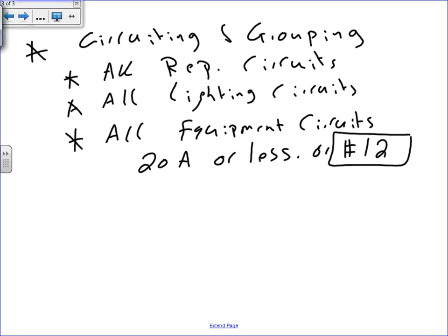Good idea, good maintenance idea. If the equipment guys need a number 10 conductor or larger, this means it's big equipment, and this means it's important equipment. This means we need to separate it from other conductors for maintenance, troubleshooting, reliability, and so forth. Could you please write this next to the CSK, Chad's opinion? So if somebody tells you otherwise, you don't see who is the idiot who told you this. Just opinion. Everybody's entitled to their opinion in the world, right?